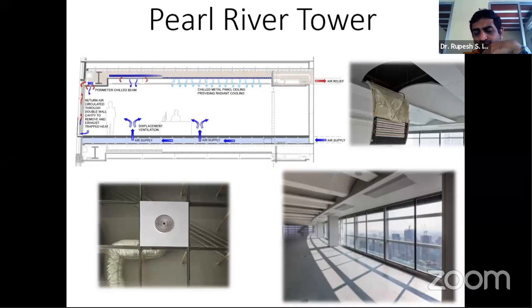Again, if you look at some of the parameters or design considerations which were used, underfloor air system again comes into this building. There is again radiant cooling which was used. These snapshots give a sense of the radiant cooling panels which were used. Again, you can see this is a false ceiling which has been converted into an active false ceiling.